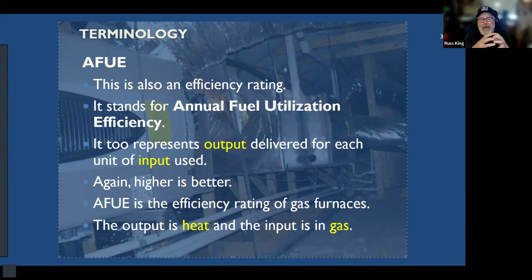Okay. So a unit of gas, of natural gas or even propane, has a fixed amount of BTUs in it. That's the maximum amount of BTUs you can get out of this gallon of gas or this cubic foot of gas. Okay. It has a fixed amount of heat in it. You put that into a furnace and you get a certain amount of heat out of it. Okay, and it's going to be less than what you're putting in because no furnace is 100% efficient. They're getting close. All right. And you take that heat that's out and you divide it by the maximum that you could have gotten out of it. And that's your efficiency. Okay. It's pretty straightforward.